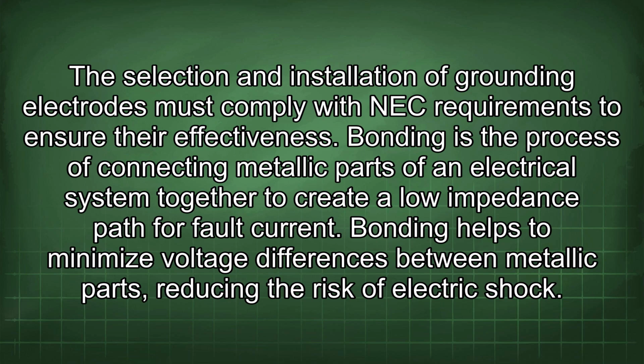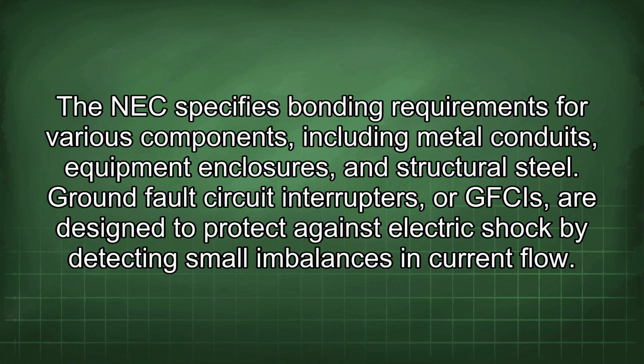Bonding is the process of connecting metallic parts of an electrical system together to create a low impedance path for fault current. Bonding helps to minimize voltage differences between metallic parts, reducing the risk of electric shock. The NEC specifies bonding requirements for various components, including metal conduits, equipment enclosures, and structural steel.